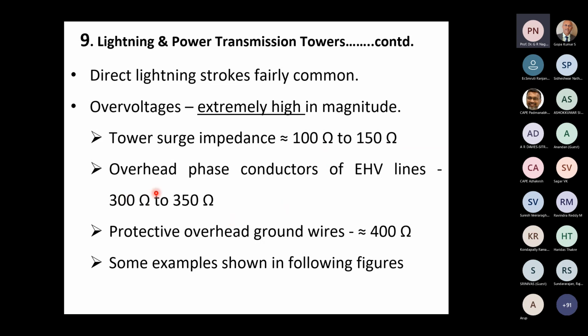The overhead phase conductors of EHV lines vary from 300 to 350 ohms. If you think of, for example, an 800 kV transmission line, it may be close to 300 ohms. If you think of a 220 kV or 400 kV transmission line, the surge impedance may be of the order of 350 ohms.